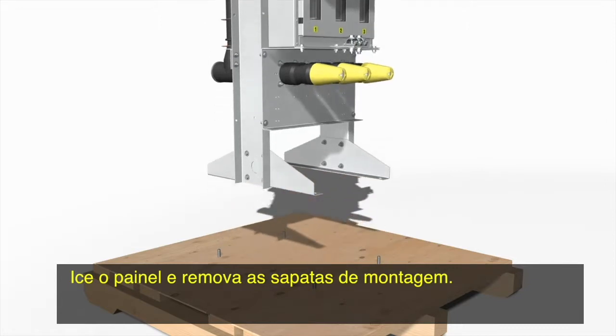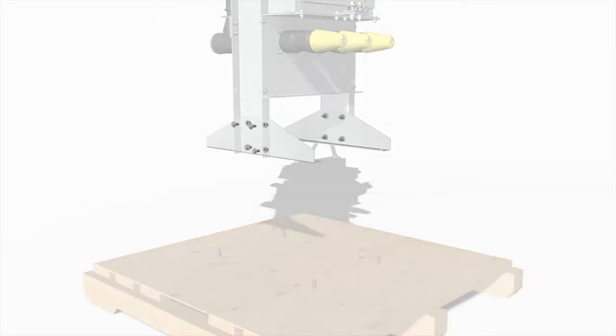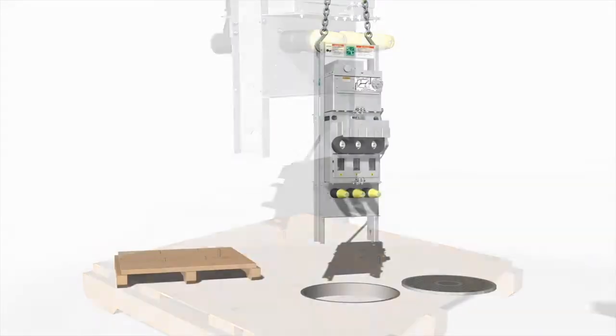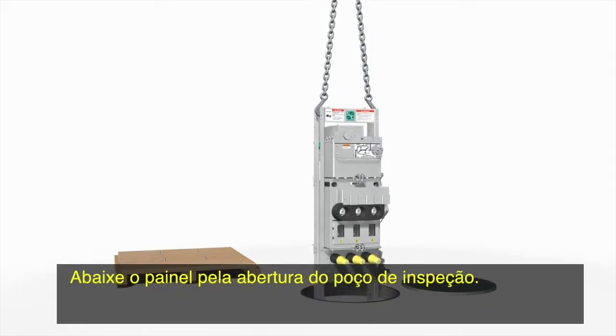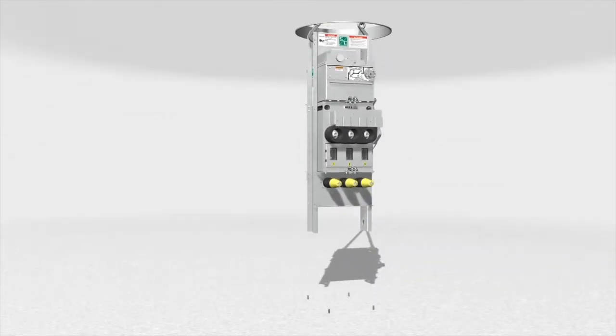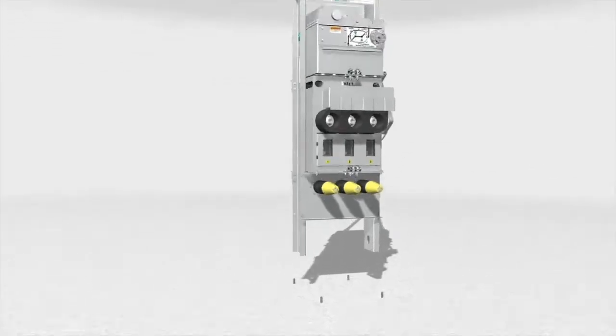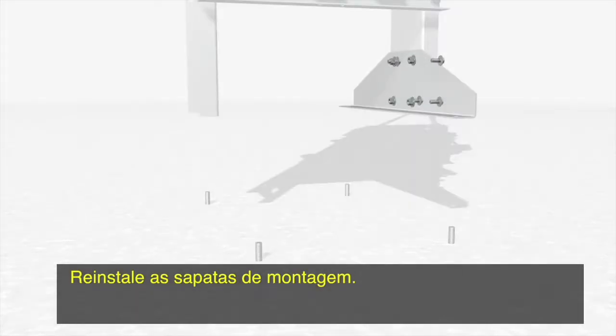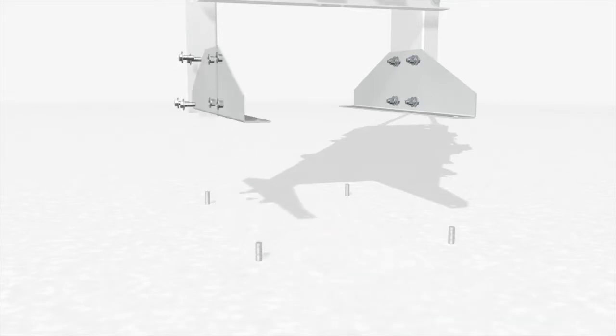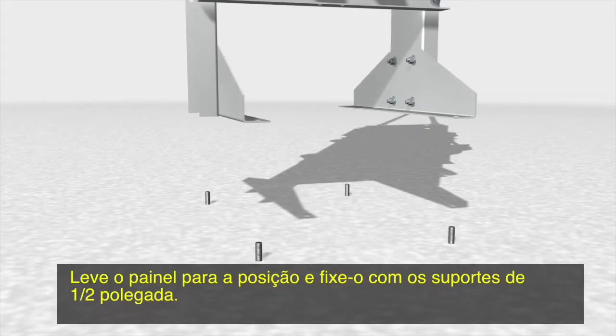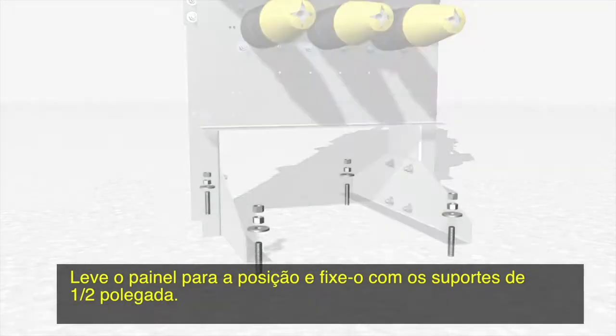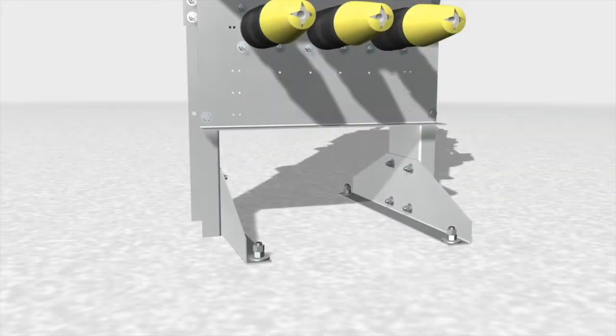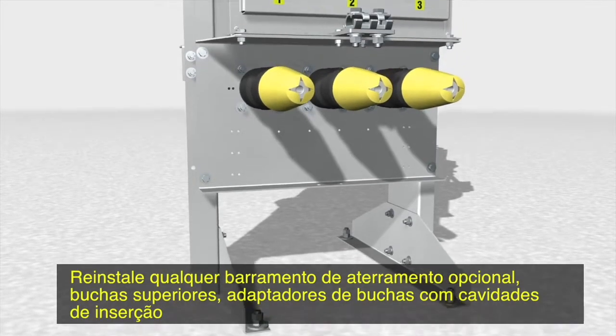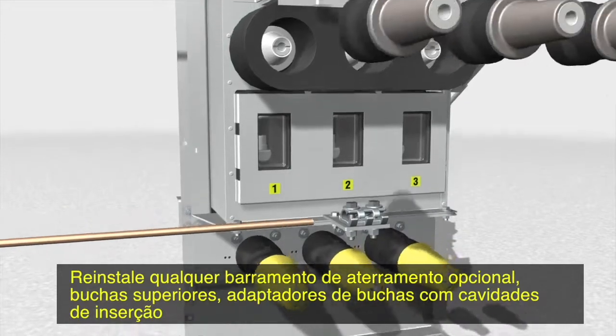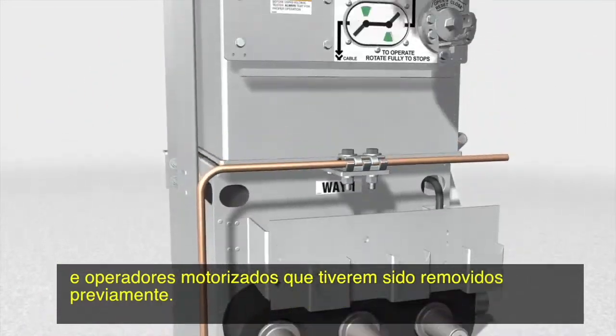Lift the switchgear and remove the mounting stand feet. Lower the switchgear through the manhole opening. Then reinstall the mounting feet. Maneuver the switchgear into place and secure it using half-inch fasteners. Reinstall any optional ground bus, upper bushings, bushing well adapters, and optional motor operators removed previously.